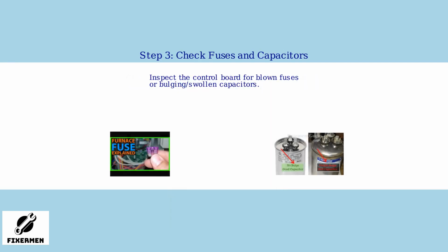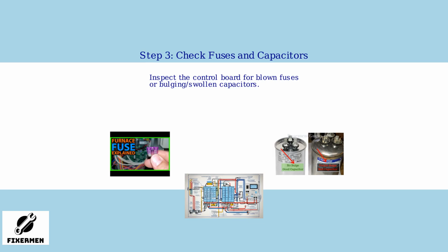Finally, check the control board for any blown fuses or obviously faulty capacitors. A blown fuse appears broken or discolored, while a bad capacitor may bulge or leak. Replace any damaged components you find.